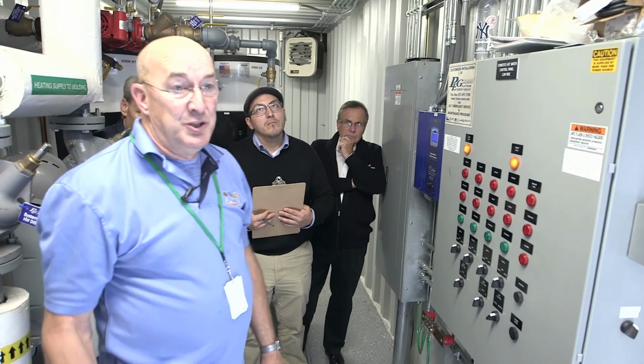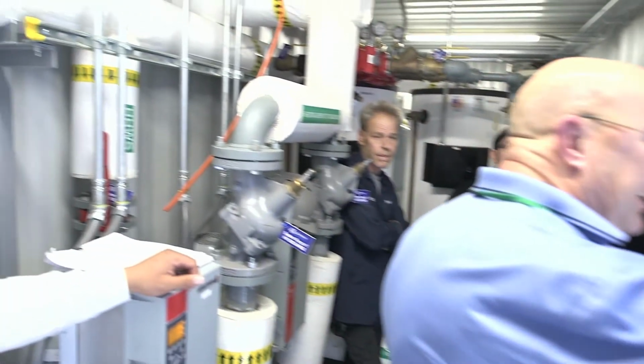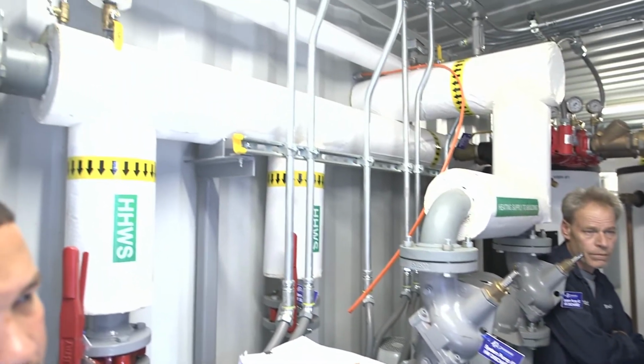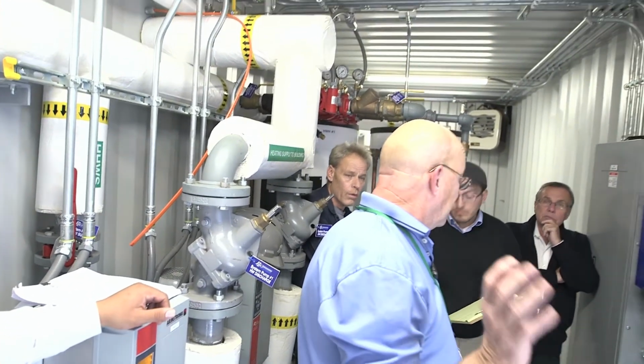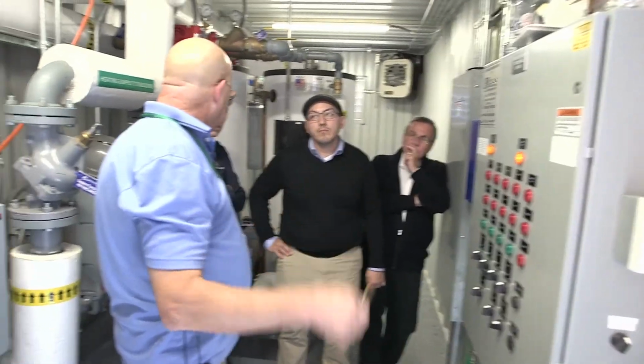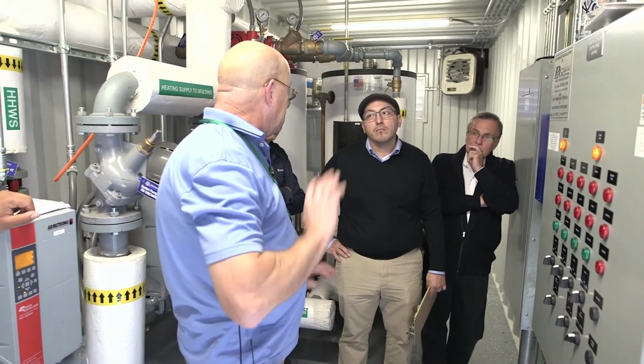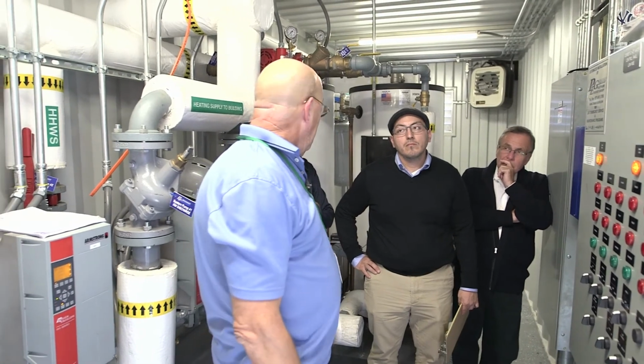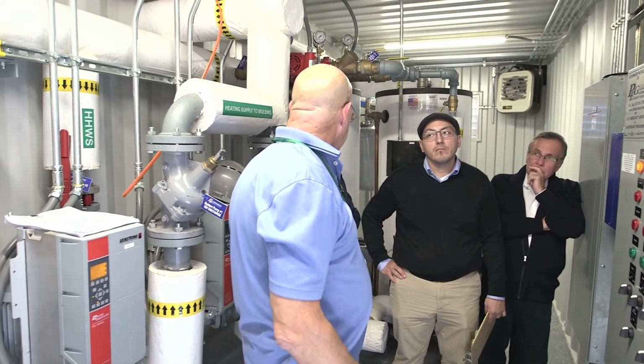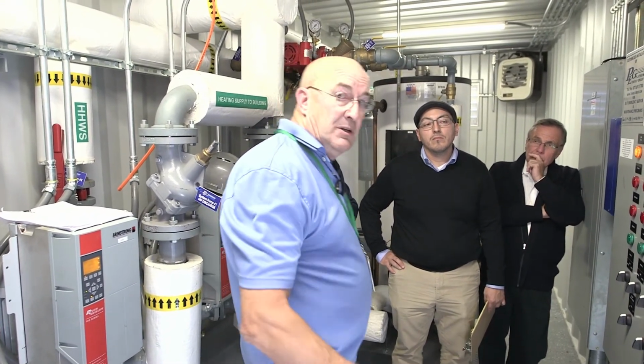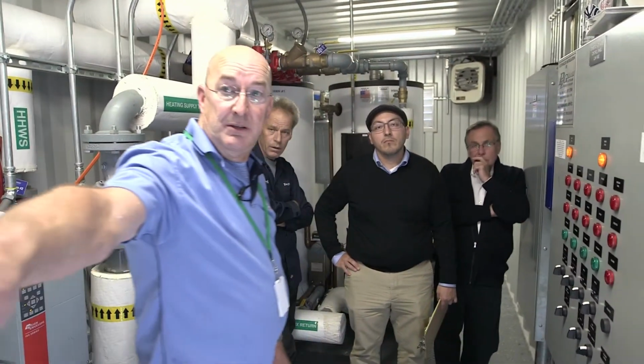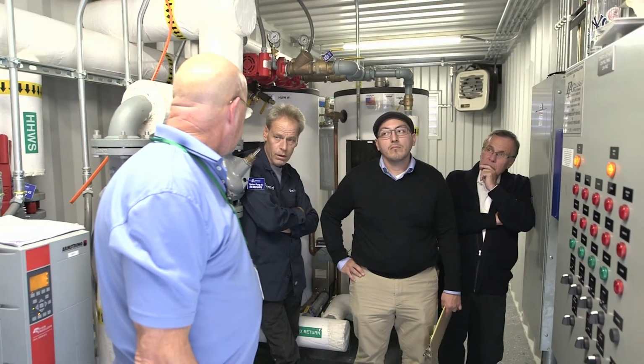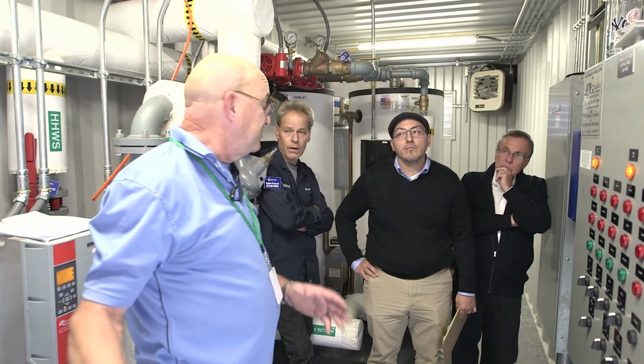You have a break glass station outside the door on the wall. In cases of emergency, you hear noises in here that you don't want to go in, shut it, break the glass. The button will pop, everything will shut down. If you're in here and something happens and you're not sure, right against the back door there, there's another emergency switch, because there has to be an emergency switch at every entrance.